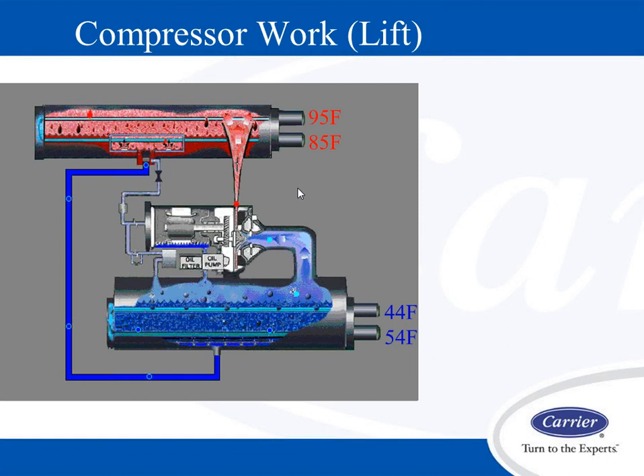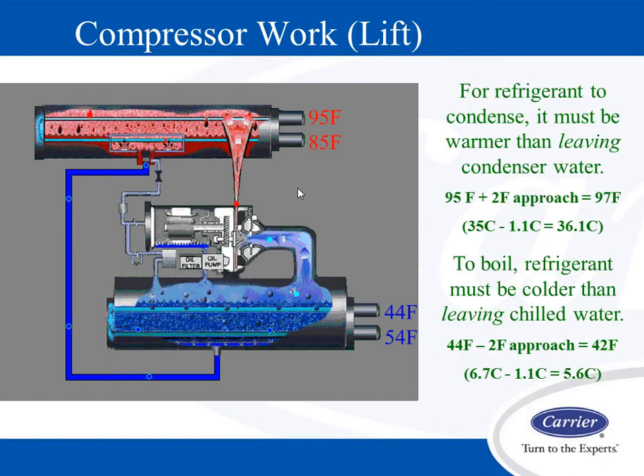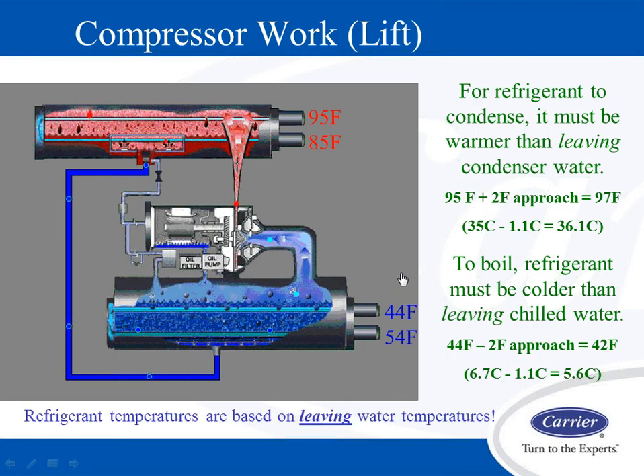When we look at the chiller operating, from the condenser side, for the refrigerant, we have 95-degree leaving water plus a 2-degree approach on the refrigerant side equals 97 degrees saturated condensing temperature. To boil refrigerant, the refrigerant must be colder than the leaving chilled water. So if we have 44-degree leaving chilled water and a 2-degree approach, we have a 42-degree saturated suction temperature. The lift of a chiller is leaving to leaving: the saturated condensing temperature minus the saturated suction temperature.